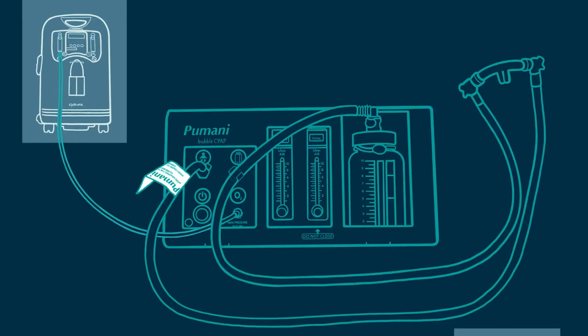You have now made a loop for the air-oxygen mix to flow. The loop goes from the CPAP machine down to the inspiratory tubing, through the prongs and then back into the water bottle. Except at the moment it can all escape through the prongs. We can close the loop by pinching or blocking the prongs.